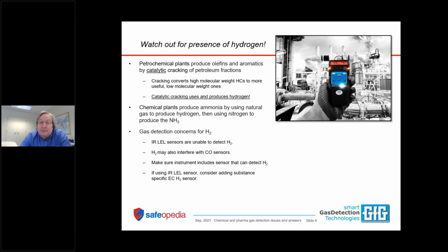Chemical plants that produce ammonia by using natural gas produce hydrogen and then use nitrogen plus the hydrogen to produce the NH3. Gas concerns from the hydrogen standpoint, well, be careful what kind of combustible sensor that you're using. There are about 4 different popular types of combustible gas sensors out there. The oldest type that has been around for a long time uses catalytic oxidation. It detects the hydrogen and any other combustible gas by burning it. An increasingly popular kind of combustible sensor now is using infrared absorbance to detect the combustible gas. That's a great way to detect methane, but infrared sensors cannot detect hydrogen. Hydrogen does not absorb infrared radiation.